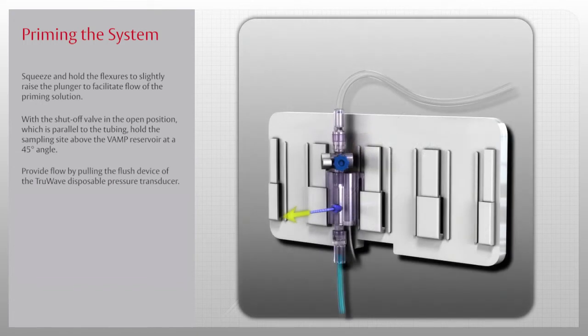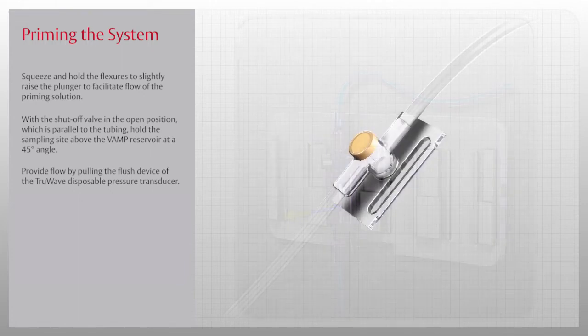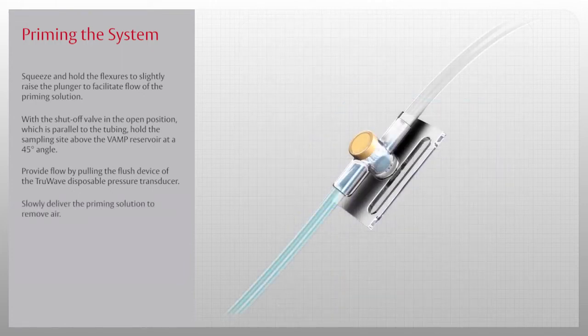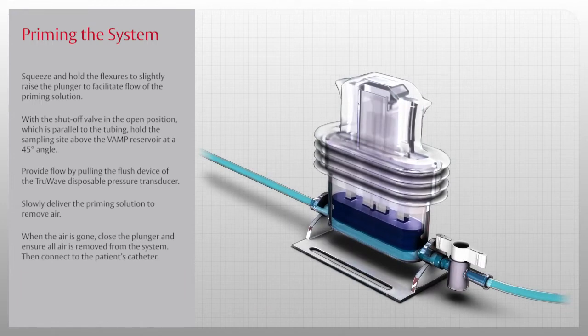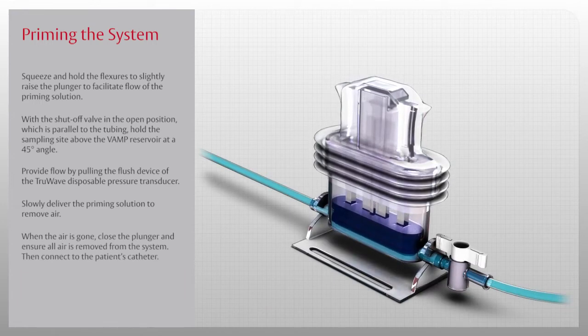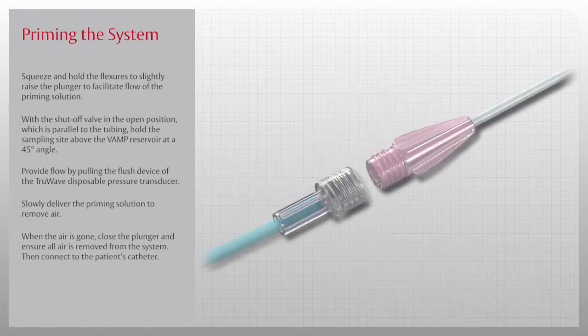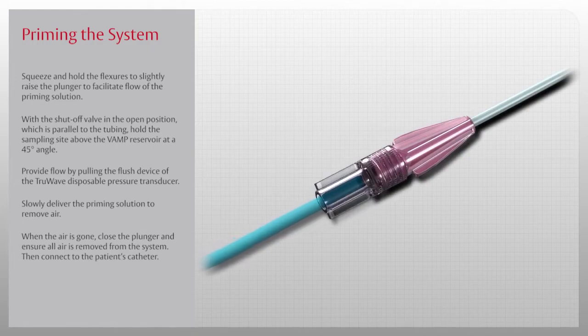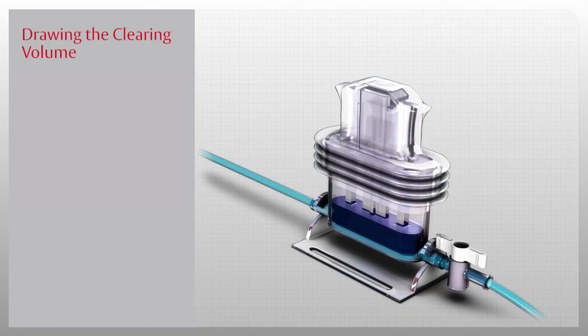Next, provide flow by pulling the flush device of the TruWave disposable pressure transducer. Slowly deliver the priming solution to remove air. When the air is gone, close the plunger and ensure all air is removed from the system. Then connect to the patient's catheter. Once the system is primed, you are ready to draw the clearing volume.